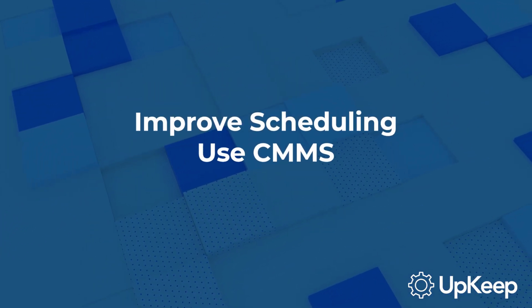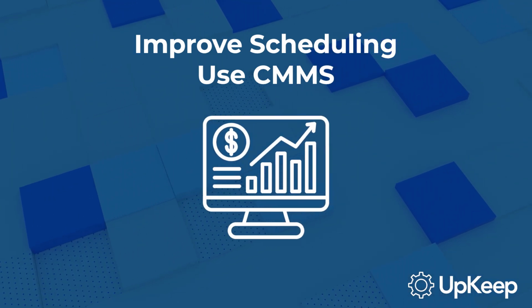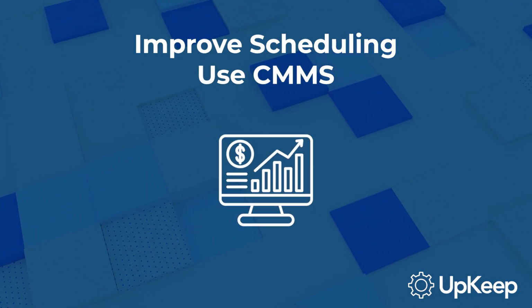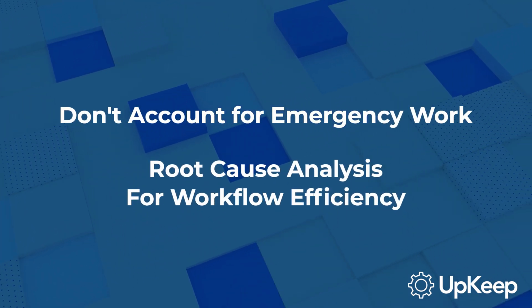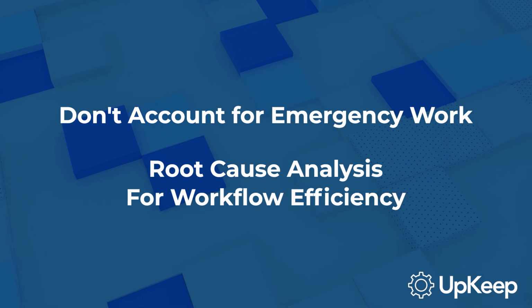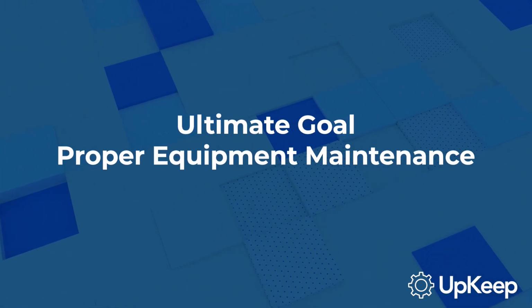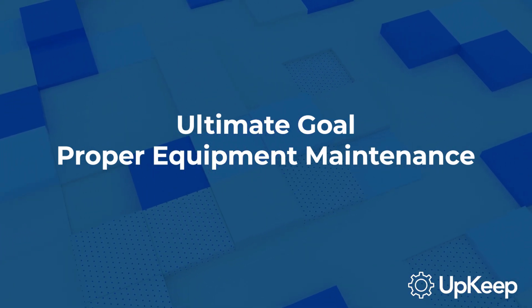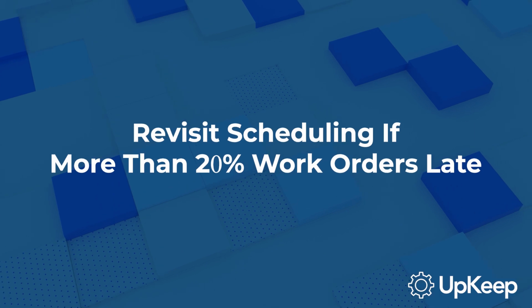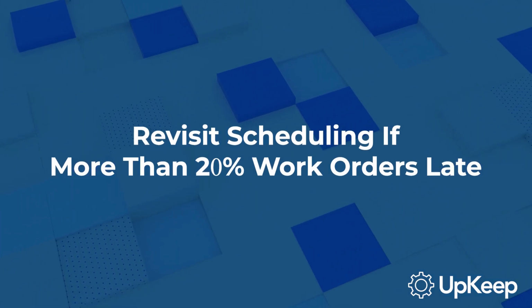To improve your maintenance scheduling practices, consider using a computerized maintenance management system to log data from work orders and assets. Don't forget to account for potential emergency work, and perform root cause analysis on your workflows to find inefficiencies. Remember, the ultimate goal is to make sure your equipment is properly maintained. So keep that in mind when scheduling maintenance work. If over 20% of work orders are completed late, it might be time to revisit your scheduling practices.